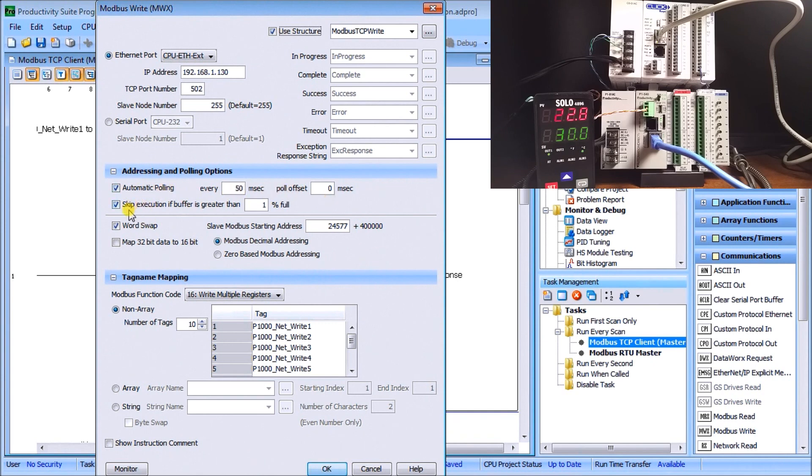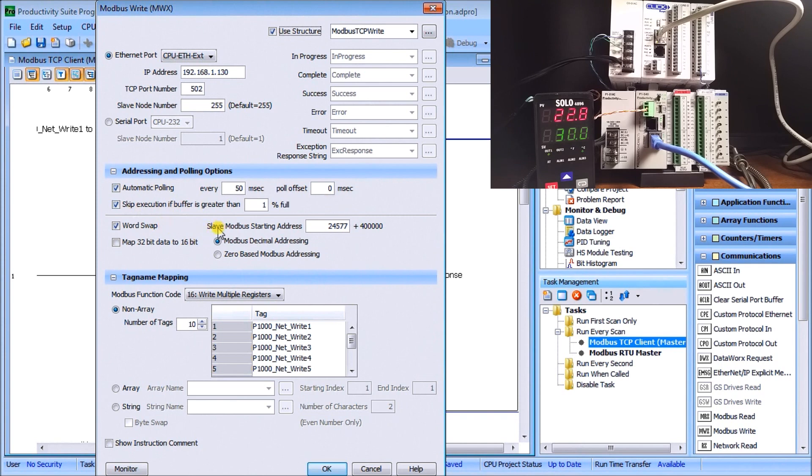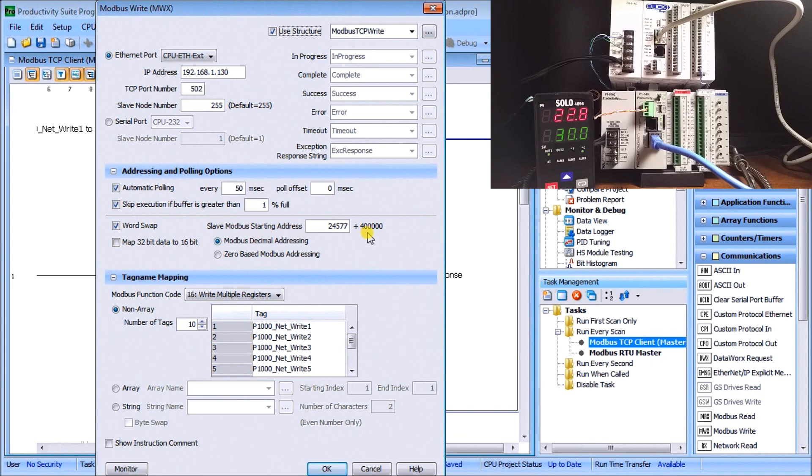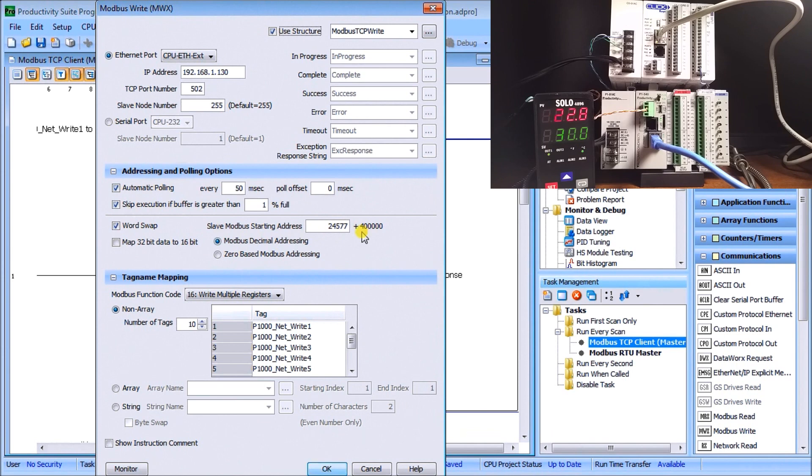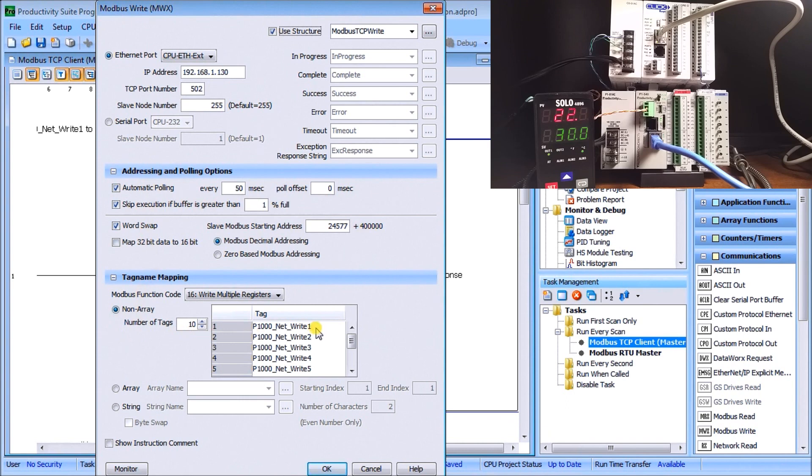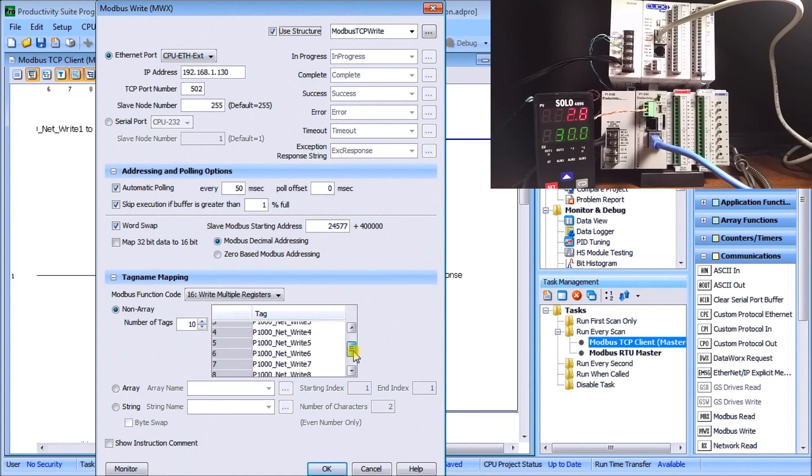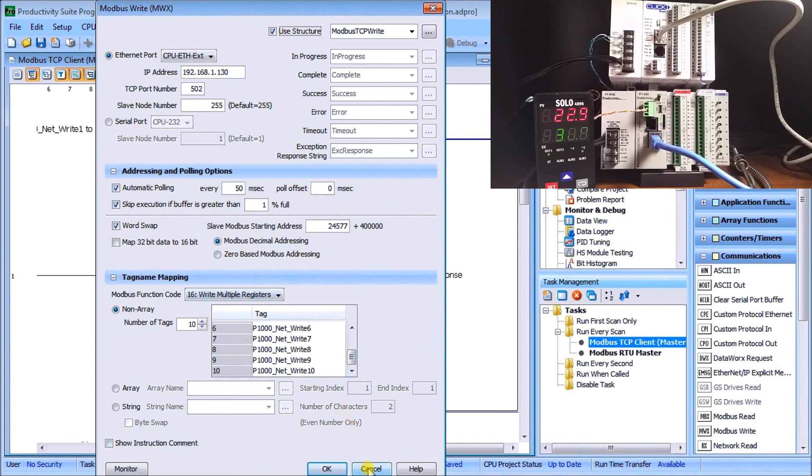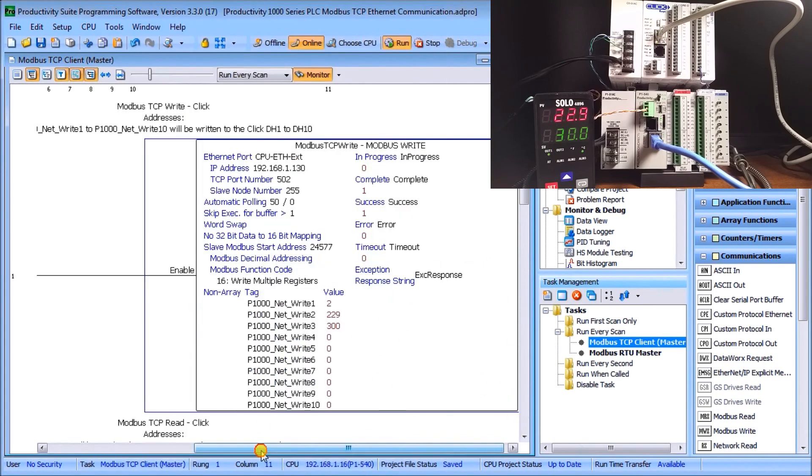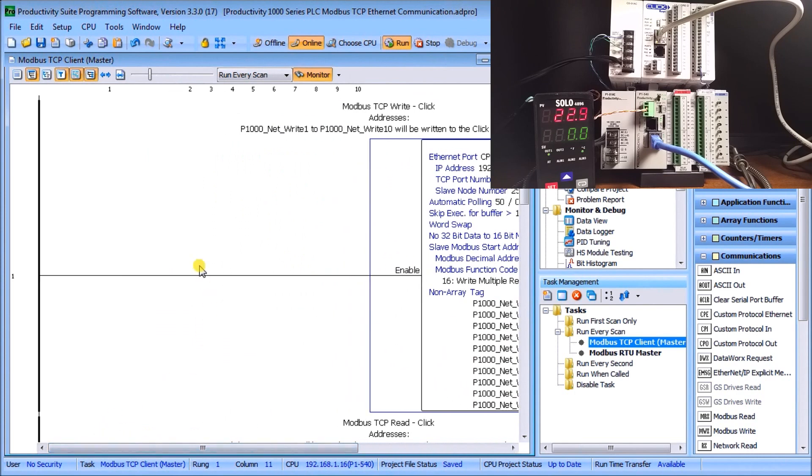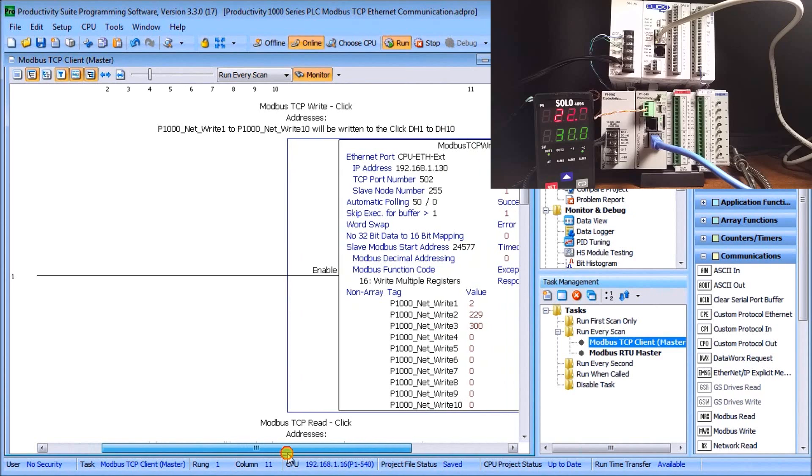I've also selected Skip Execution if Busy and if Buffer is Greater Than One Percent. Then our start word or word swap. Our slave Modbus starting address is 424577 plus the 400, or the 40,000 or 400,000 that's in there, so that creates our Modbus address that we looked at before, which was actually DH1. Then we go to our tag name, so we're using non-array tags. We're going to do ten tags and we're going to start down at DH1, which will map into our P1000_Net_Write1, which will map into that first Modbus address and that takes us all the way down to ten. That's our write instruction, and you'll notice on the left-hand side column we don't have any instruction—it automatically will start writing for us.